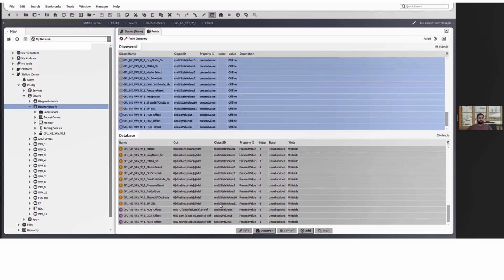So the basic gist of what I'm getting at is, for you to import this EDE, every manufacturer or vendor you're dealing with has to provide you an EDE, which is a BACnet standard. Every programming tool, let's say Honeywell has one, Johnson has one, or other vendors have their own programming tool, they should provide you one as such, which you can import from the same EDE BACnet importer which you just shared, right?